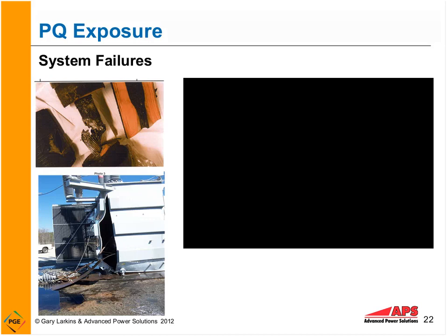And this is actually at a golf course in Florida, where they caught this transformer, and we can see the transformer. This is a catastrophic failure. It doesn't occur that often, but if it does, how are you protected against what may be sent into the power grid here from this type of event, this type of failure? Do you have adequate protection? I've seen transformers within customers' facilities, their own transformers, do this same type of thing and actually cause, in one case, a whole computer lab to fail equipment because they didn't have adequate protection.